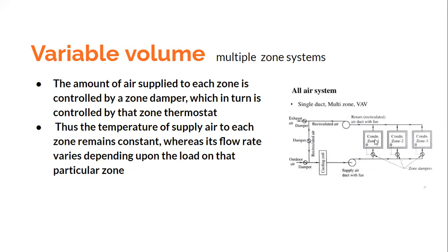So you sense if the cooling load is more, that is, more heat is to be removed, then you might change the zone damper and allow more air to flow. If your cooling load is less, then you would allow less air to flow through it. This is how a variable flow system would control and maintain different zones, that is, different temperatures within the different rooms.